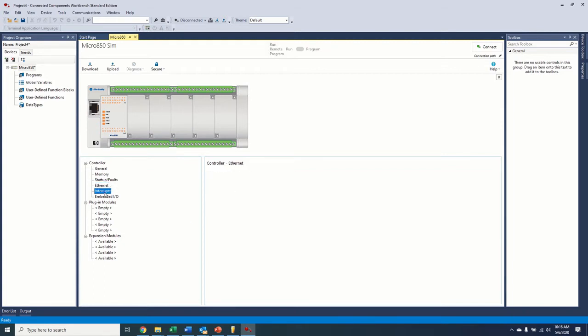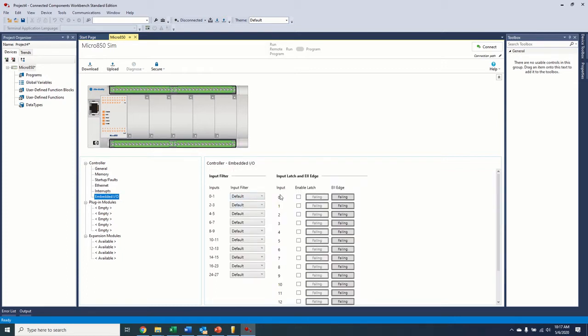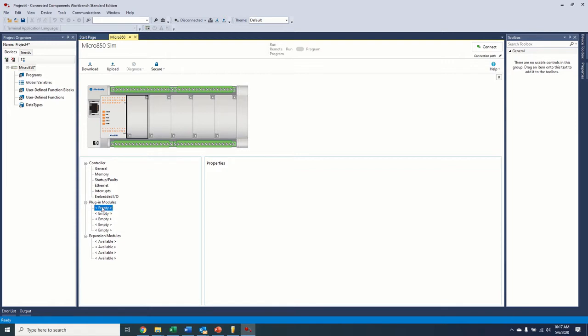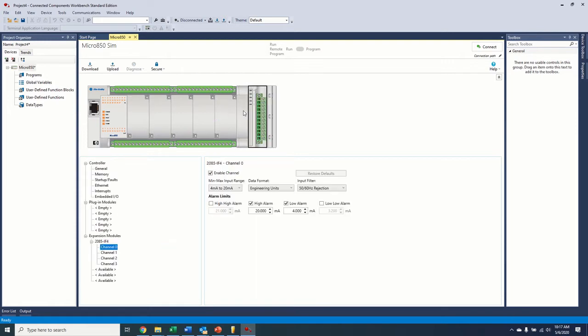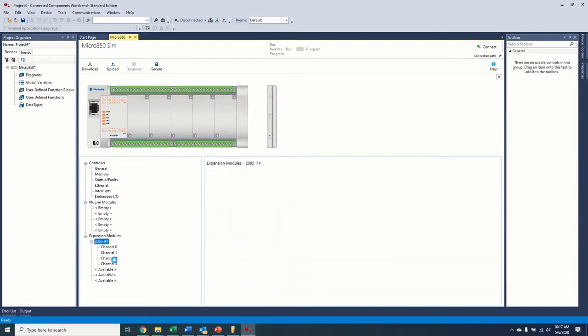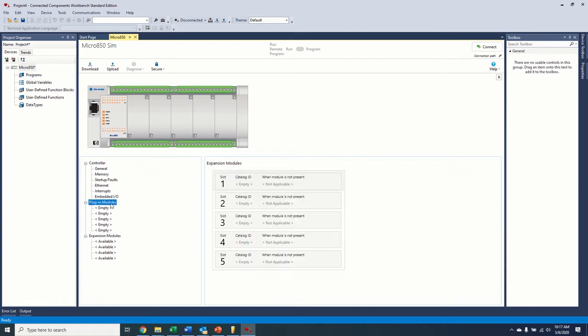Ethernet, we'll cover that in a second. Interrupts, so those of you that have programmed with 500, 5,000 know you can interrupt the program, the running program on an event. So that's what this is here for. And then the embedded I/O, this is just if you wanted to put a filter on here or a latch, just like you would with an I/O module in 5,000, you can set that up here. Plug-in modules and expansion modules. This is where if you had any plug-in modules in any of these, you could right-click on this empty, add whatever your plug-in module is, or your expansion module, and it would show up at the top here and allow you to configure it here. We're going to go ahead and get rid of that since we don't have any of those here.